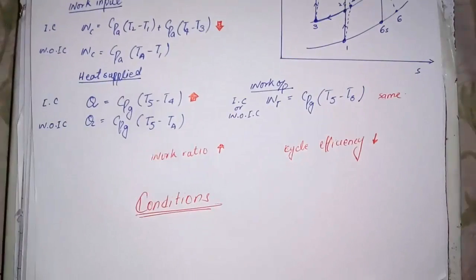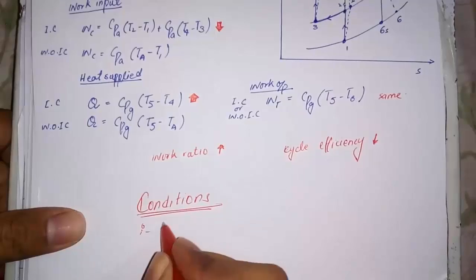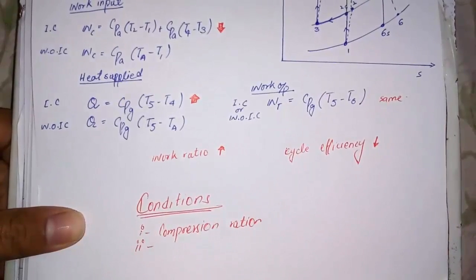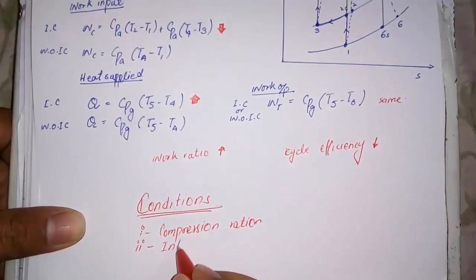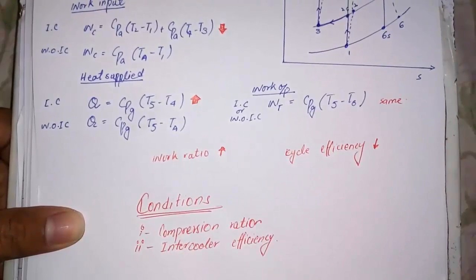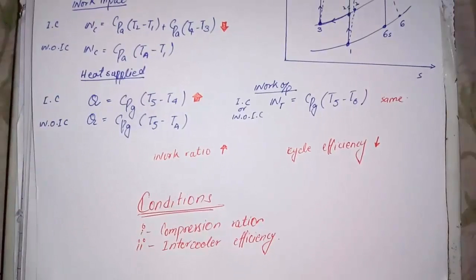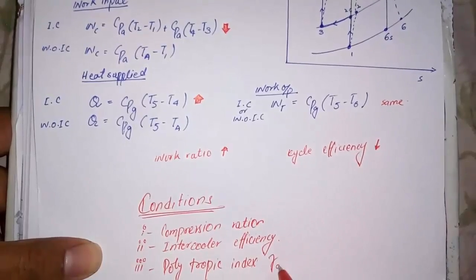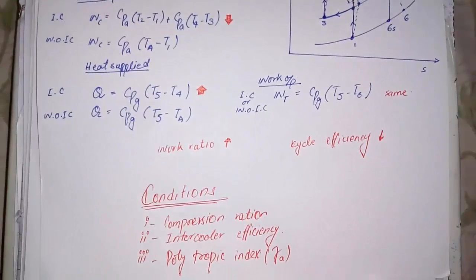To use this method to improve the gas power plant, there are three conditions. First is compression ratio must be same in each compressor. Second is intercooler must be 100% efficient, means it must make the temperature which was at the inlet of the compressor after each stage. Third is polytropic index gamma must be same for each stage.